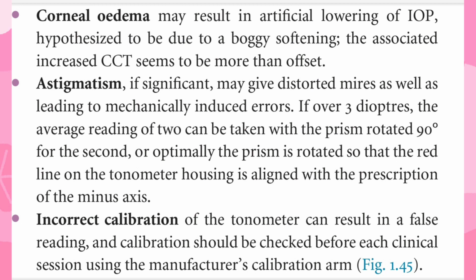Incorrect calibration of the tonometer can result in a false reading, and calibration should be checked before each clinical session using the manufacturer's calibration arm, figure 1.45.